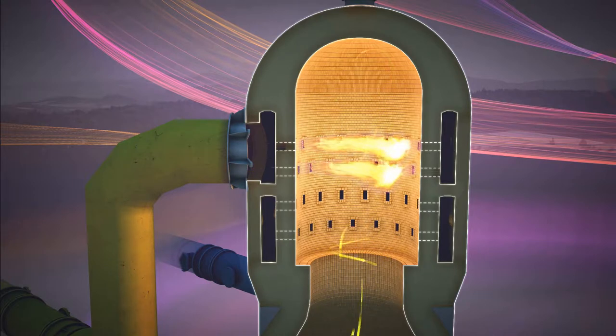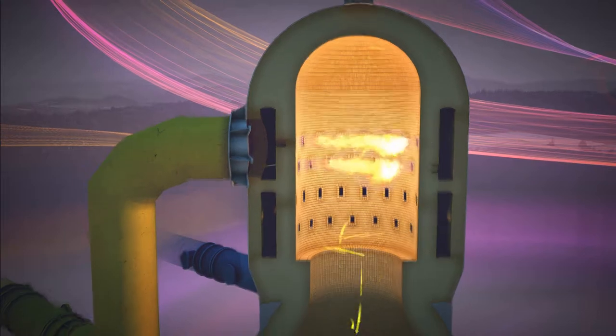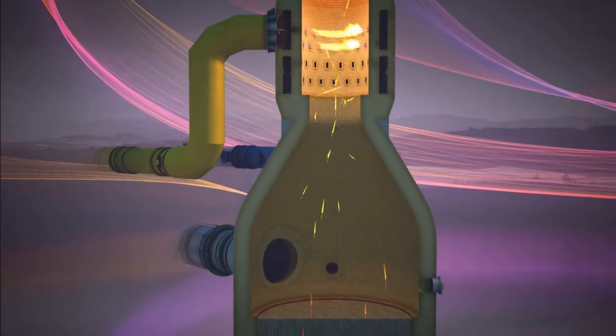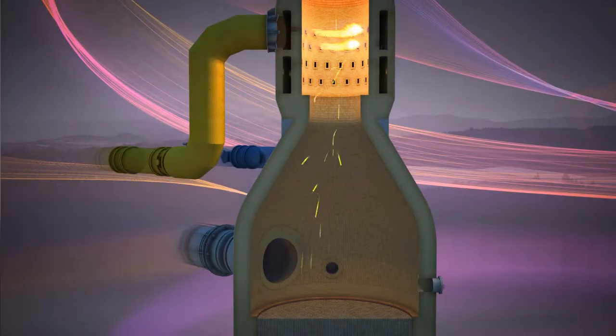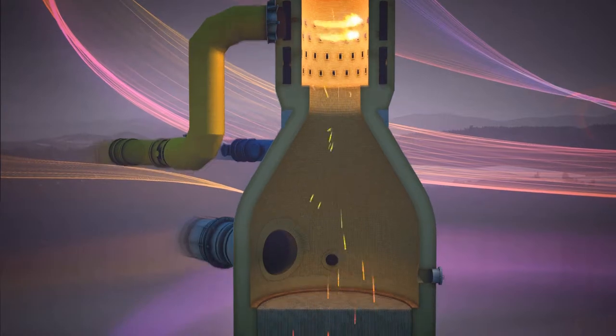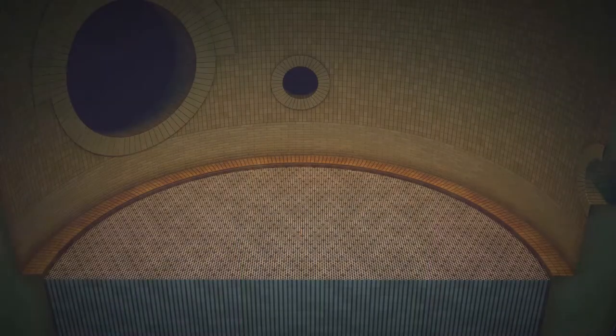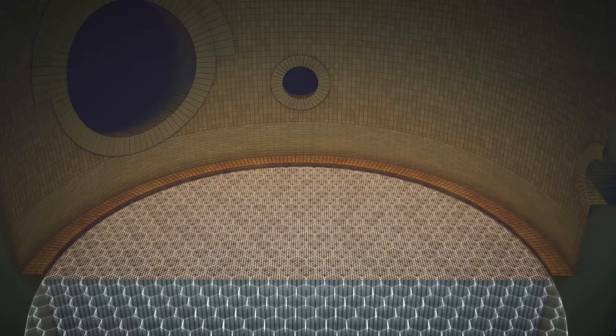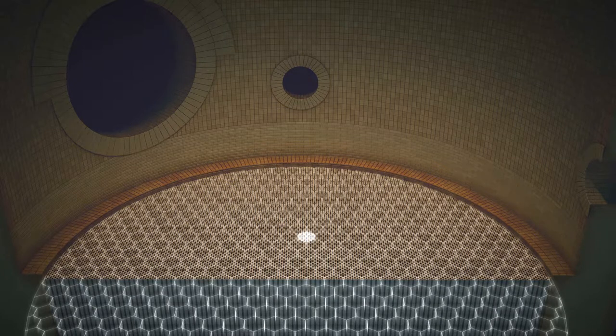Flame pulsation during combustion is completely eliminated in Kalugin stove design. There is no flame impingement against the brickwork and no local overheating, which provides symmetric distribution of temperatures over the dome, checkerwork, refractory lining, and shell. As a result, thermal stresses are reduced and stove durability is improved.